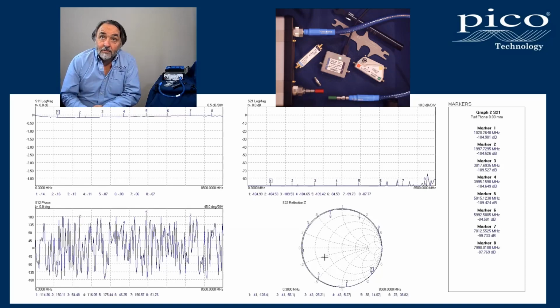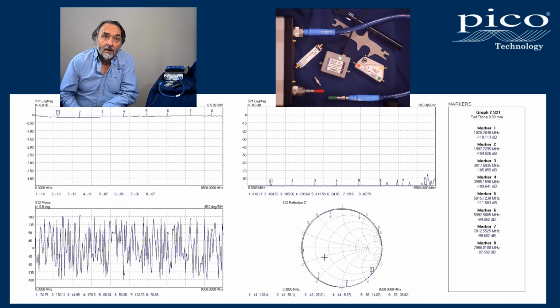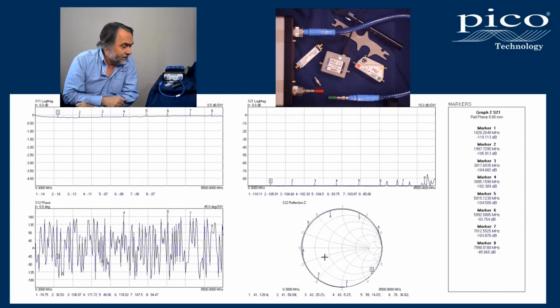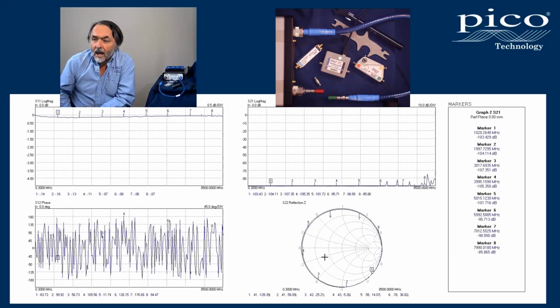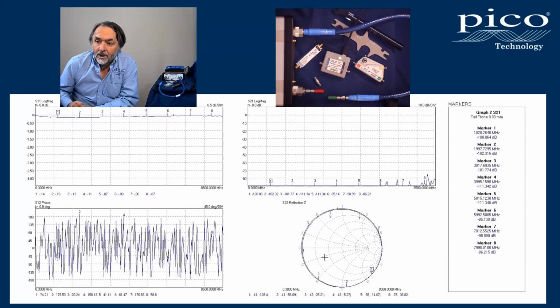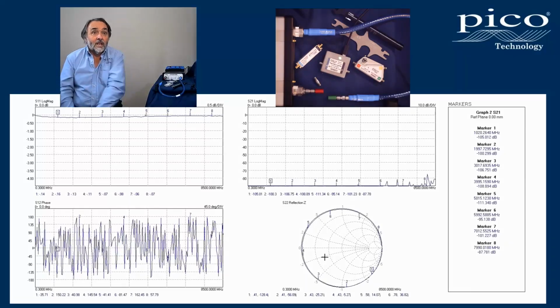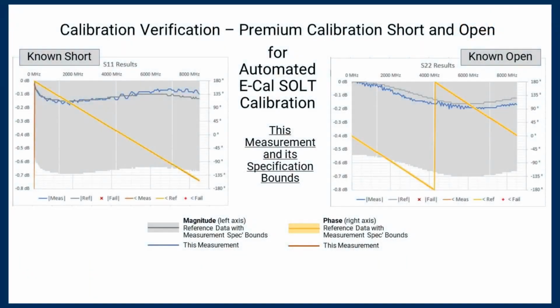Well, we can do exactly the same as we did with the check standard. We can use the compare data utility. We can take the data that was provided with the calibration pieces, and compare that with the measurements that we're making here. And this is what we get. So here we have the two S parameter plots. We have the short on the left, S11, and on the right we have the open plotted alongside its reference. We can easily see magnitude of reflection, blue, matching very well to the reference data, the grey trace. Certainly well within specification, the light grey shading.